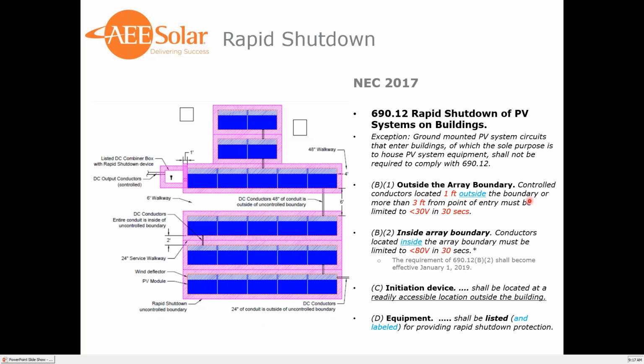The code actually does specify the initiation device shall be located at a readily accessible location outside of the building. And the equipment shall be listed and labeled for providing rapid shutdown. So previously it was identified, which means you could almost use off-the-shelf equipment as long as it was not outside of the scope of the use or the equipment parameters. You could assemble items to qualify as a rapid shutdown device, but they're pretty much saying now that it has to be labeled and listed for rapid shutdown use.